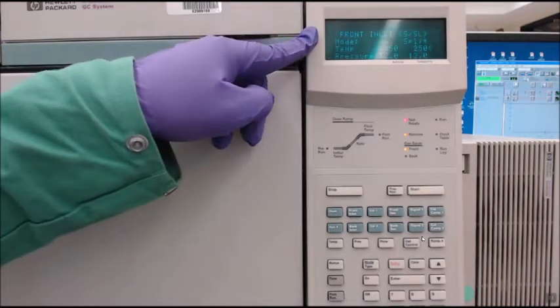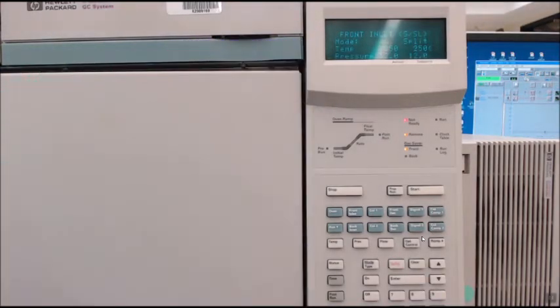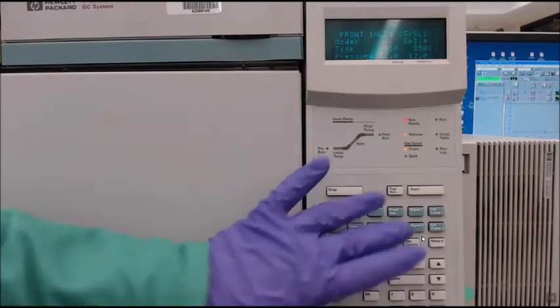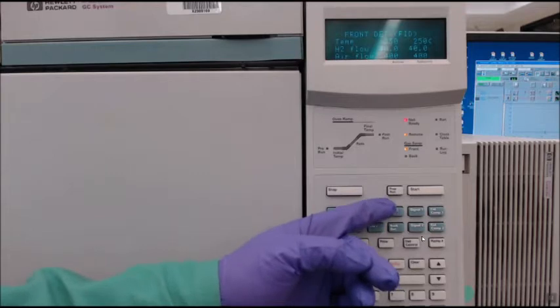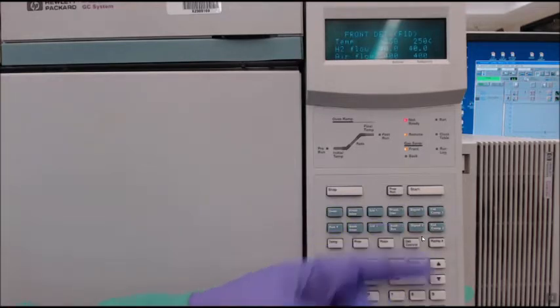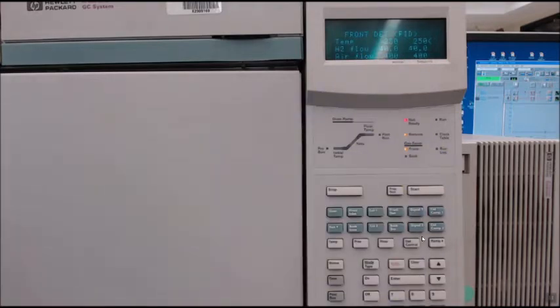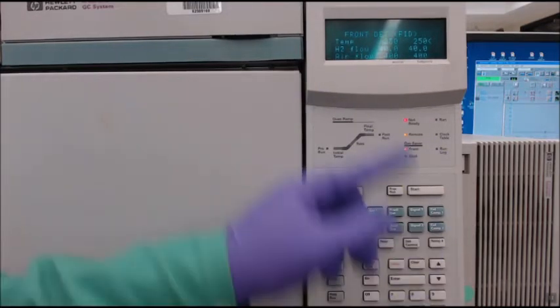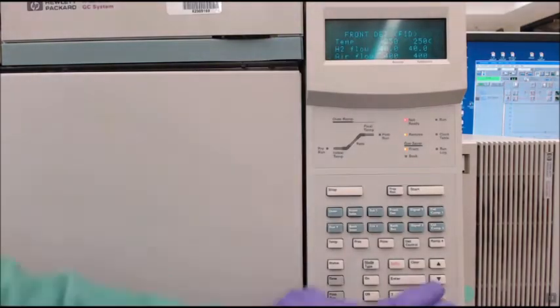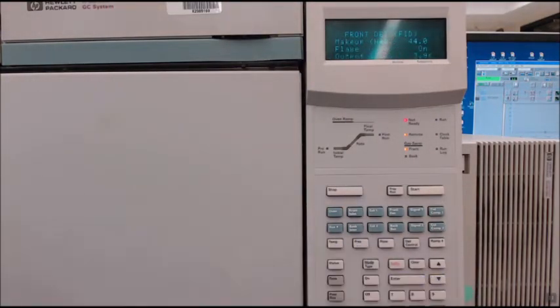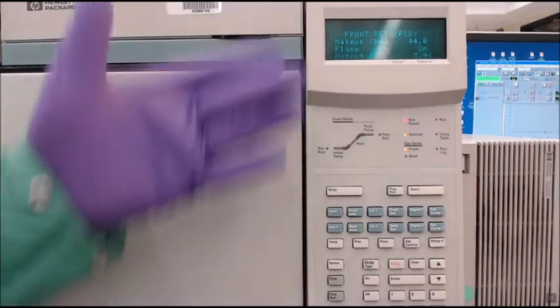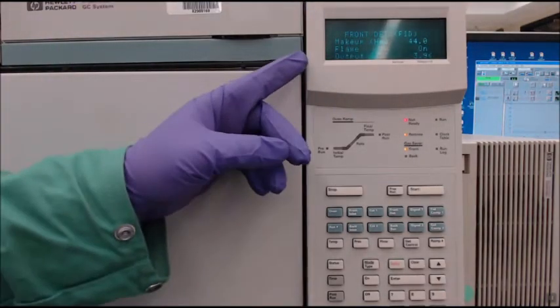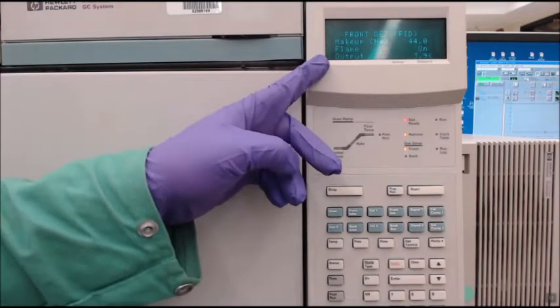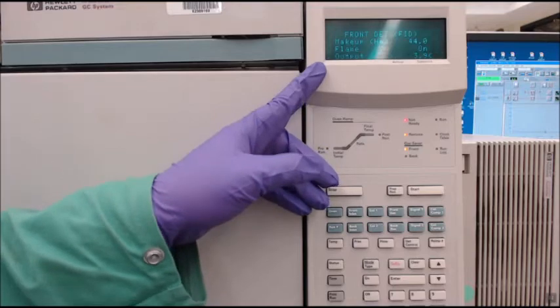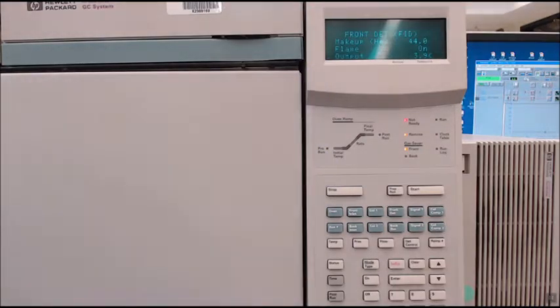We are in split mode. We are at the correct temperature. Everything is good with the inlet. The final thing you'd want to check is your detector. Again, we are using the front detector. If this were on a back detector, you would use the back detector button. We are at temperature. We have good hydrogen and airflow. As you can see, we have a 10 to 1 ratio. And if we scroll all the way down, we can see that our flame is on because the machine tells us that it is. The other way we know that our flame is good is that our output is greater than 1. If the flame were off, it would read about 0.1, maybe 0.2. So we know everything is good to go, and we are ready to run our sample.